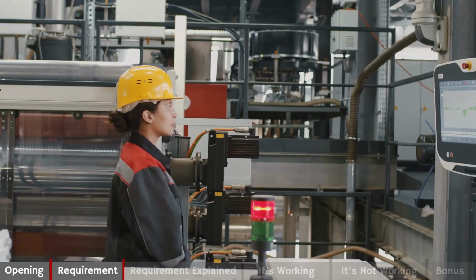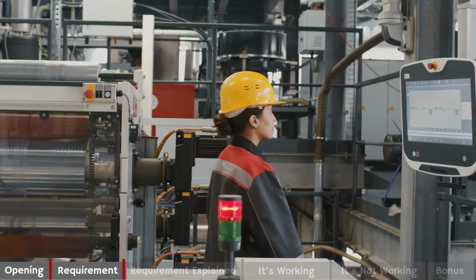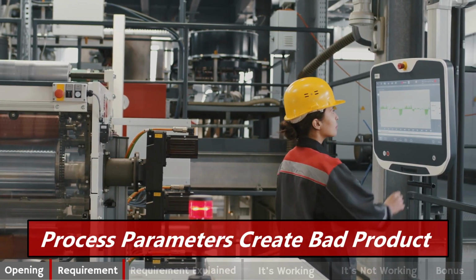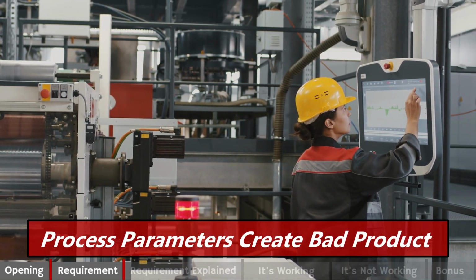Our topic, edge of failure, is used to fulfill some of the requirements for process validation, which come directly from 13485 section 7.5.6 and 820.75. Edge of failure in 5 words. Process parameters create bad product.